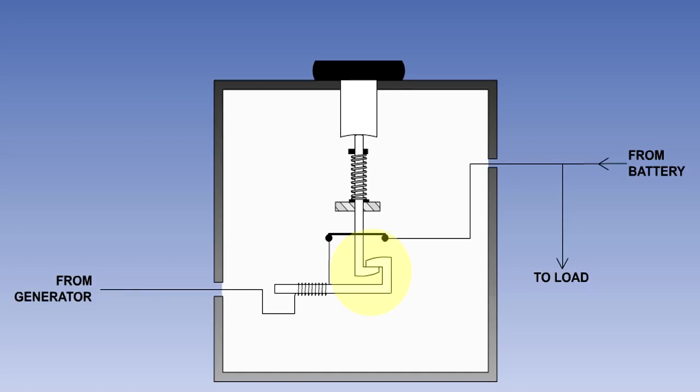The reverse current circuit breaker contains a latch mechanism, which is holding a set of contacts closed. The latch mechanism is held closed magnetically. A coil wound around the latch mechanism produces a magnetic field, which helps to hold the mechanism latched when the current flow is in the normal direction.